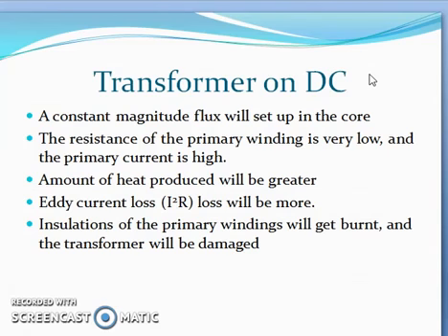Resistance of the primary winding is very low and the primary current is very high, much higher than the rated full-load primary current. As a result, the amount of heat produced will be greater and eddy current losses will also be more.